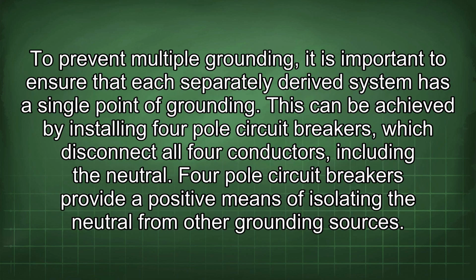To prevent multiple grounding, it is important to ensure that each separately derived system has a single point of grounding. This can be achieved by installing 4-pole circuit breakers, which disconnect all 4 conductors, including the neutral. 4-pole circuit breakers provide a positive means of isolating the neutral from other grounding sources.